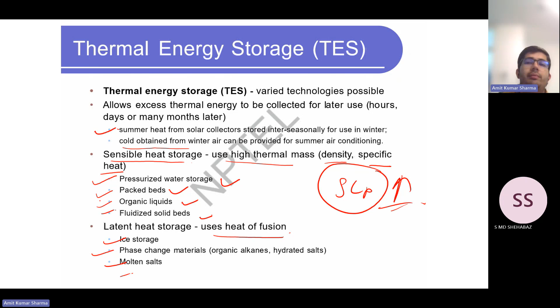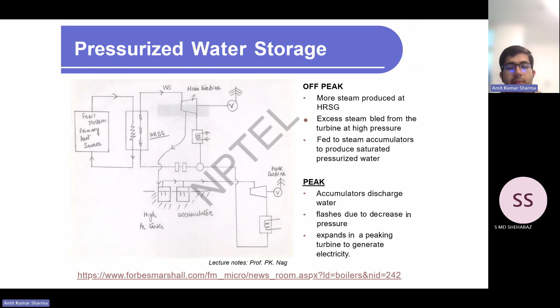So during off-peak, more steam is produced at the HRSG and excess steam is bled from the turbine at high pressure, fed to steam accumulators to produce saturated pressurized water. And during peak time, the accumulators discharge; the water flashes due to decrease in the pressure. Because the water was stored at high pressure and now the pressure is released, it directly flashes into vapor and expands in the peaking turbine to generate electricity. So this is the kind of system.